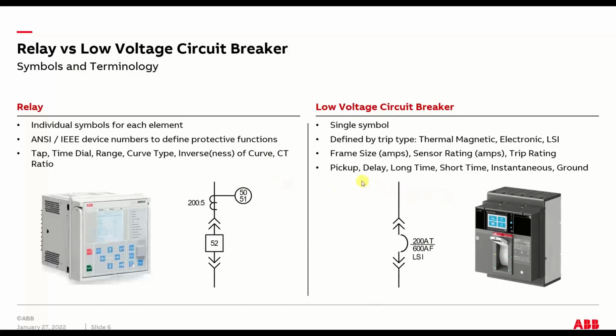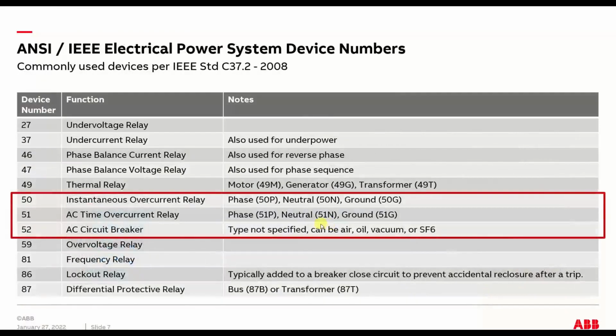Equivalently in the low voltage world, you'd have things called pickup, delay, long time, short time, instantaneous, ground. The CTs in a breaker like this are called sensors. So completely different vocabulary, but both describing exactly the same physical phenomenon and basic kind of components. Here's a breakdown of the device numbers, the ANSI IEEE standard device numbers.